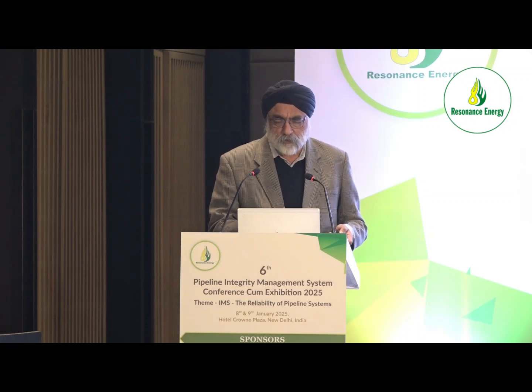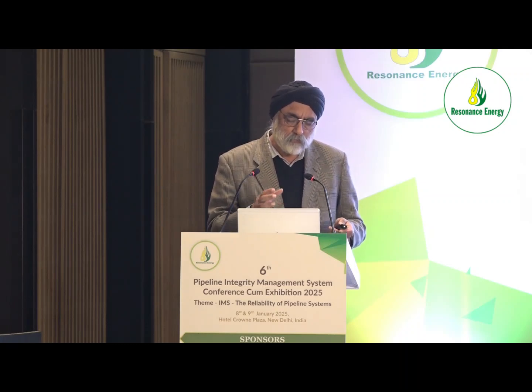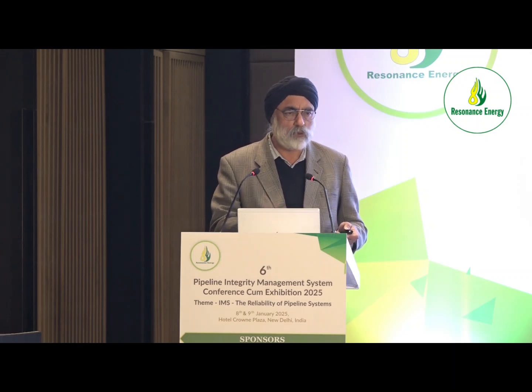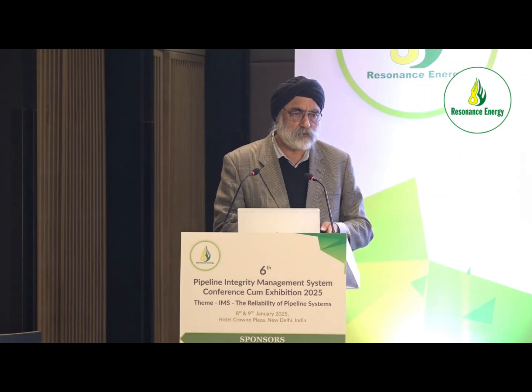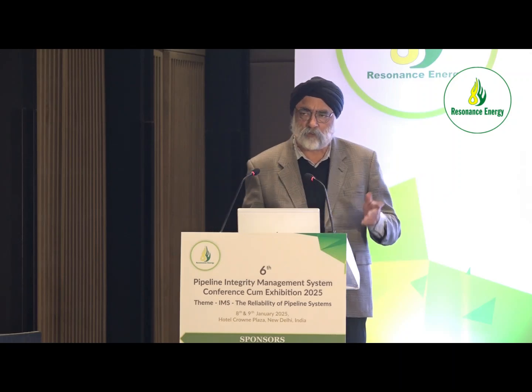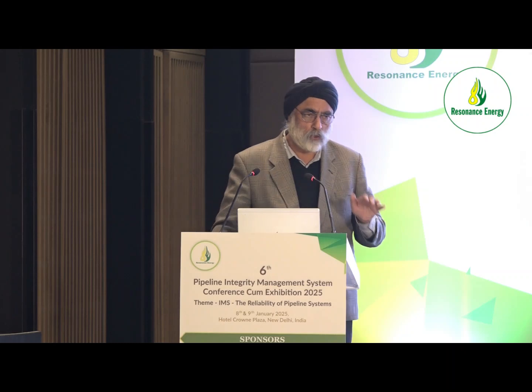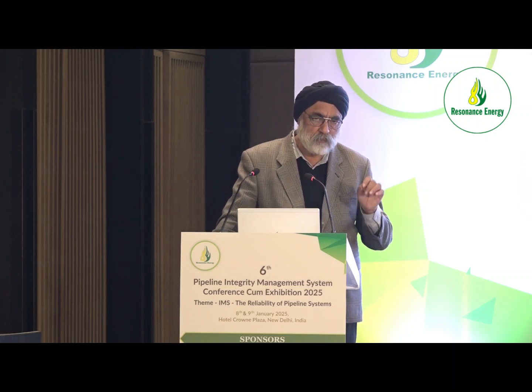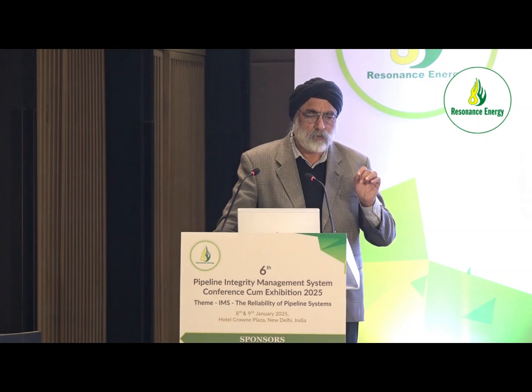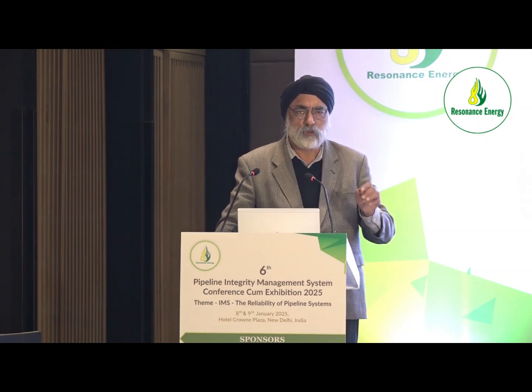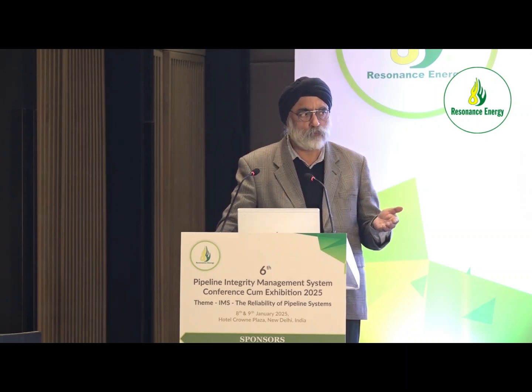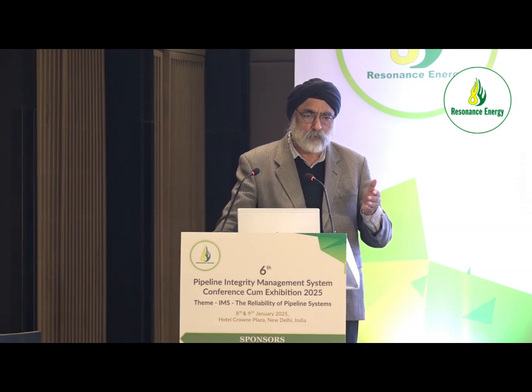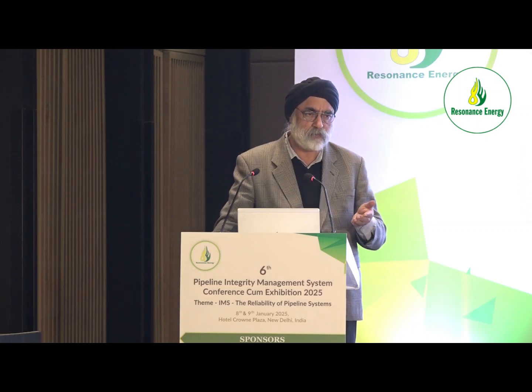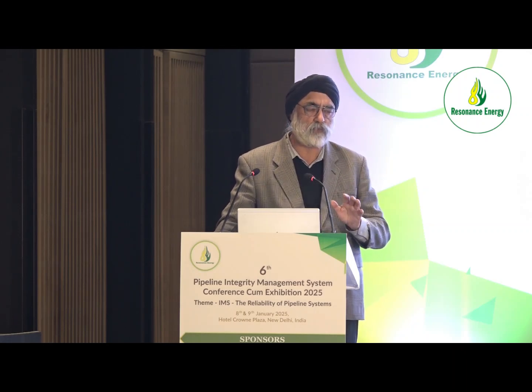Just one or two more slides. This shows the red arrows as CP currents entering. For AC, most pipelines in the city will show 2, 3, or 5 volts. The earlier thought process was that 15 volts meant the line is okay, but that was from a shock perspective. The latest standards say even 1 or 2 volts can cause AC current to leak into the soil, which can increase the rate of corrosion. So we have to measure the current density to find out whether the pipe is protected or not. Current density measurements require 24 hours of data logging.